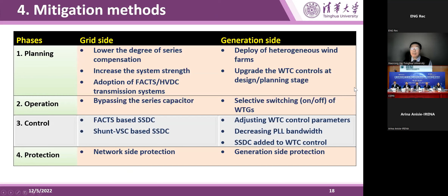This is an example of a grid-side subsynchronous damping controller. It adds positive resistance at the target oscillation frequency. A customized shunt converter is used to inject the subsynchronous currents into the grid. A 10 megawatt prototype has been developed and installed at a substation in a wind power system to dampen the oscillation. The effectiveness was verified through experiments.